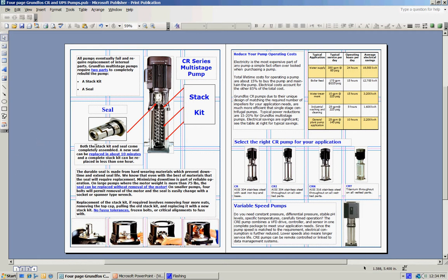In the case of the Grundfos unit, the seal comes in one complete assembly, and for a smaller size pump it essentially involves releasing the motor coupling, removing some bolts, and taking the motor off the top of the pump. You can simply leave the pigtail attached, extract the old seal by using a hex headed wrench to pull it out, and install a new seal. There's a spacer ring in here to set the proper gap. Put the motor back on, couple it back up, and you're back in business. That whole process should take about 10 minutes.